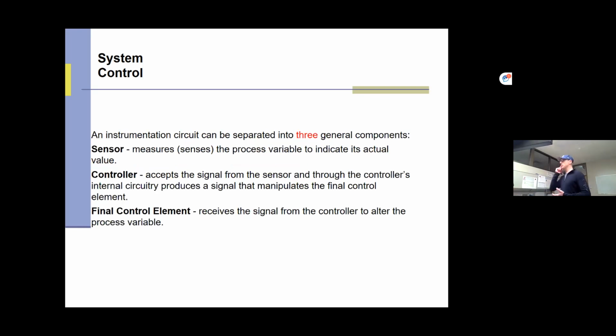So some of the things we just saw there is an instrumentation circuit, and that's 3 big components. You saw the sensor, right? The level transmitter is what we used in this case. It senses the process variable. It's saying the level in the tank or the pressure or the flow or whatever we're measuring. It says, hey, I'm providing this signal, the 4 to 20 milliamp signal. It's going to send it to my controller. We called our controller a programmable logic controller, or PLC.